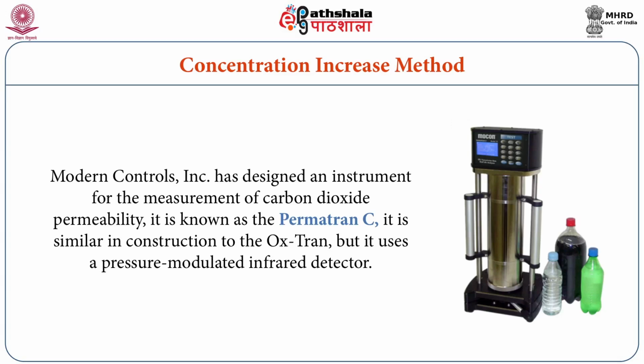Modern Controls Inc. has designed an instrument for measurement of carbon dioxide permeability. It is known as Permatran C. It is similar in construction to the OX-Tran, but it uses a pressure modulated infrared detector.